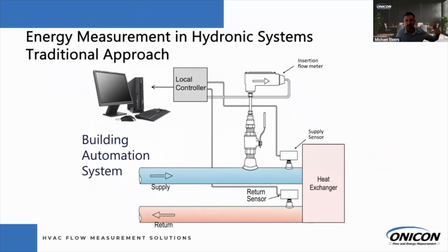So when you think about when ONICON started back in the 80s, we only sold flow meters. And so what happened was we'd get a phone call 3 years later and they said, hey, your flow meter is not working right. We're like, hey, we built, calibrated, and configured it for your specific application. Why don't you think it's correct? And they said, our BTUs aren't adding up. And so that's when ONICON started diving in to understand where these inaccuracies are coming from. Because typically they would just take a calibrated flow meter to our RTDs and go back to the building automation system.